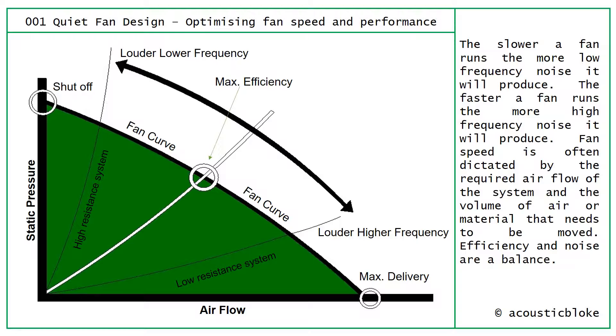Looking at optimized fan speed and performance on a graph — with airflow along one axis and static pressure along the other — the maximum efficiency point is somewhere along that curve, usually in the middle, balancing between louder low frequency noise and louder high frequency noise. As system resistance gets lower, frequency goes up; as it gets higher, frequency goes down. The lower the fan runs, the more low frequency noise it produces. Fan speed is often dictated by the required airflow, so efficiency and noise are always a balance.